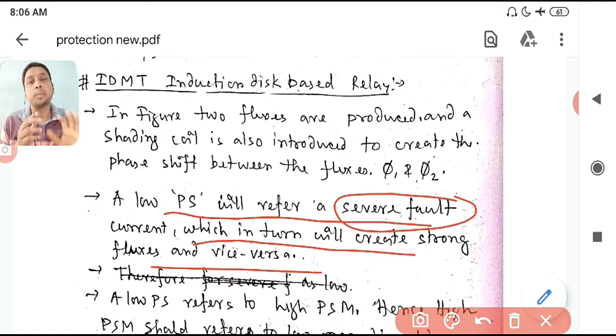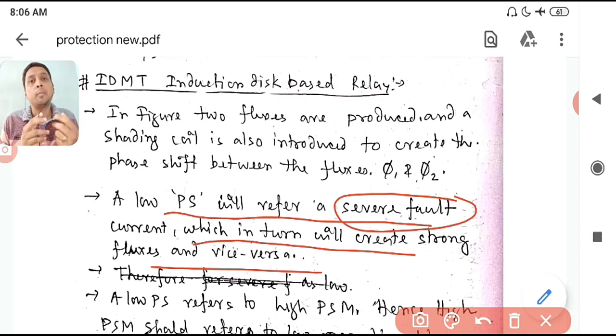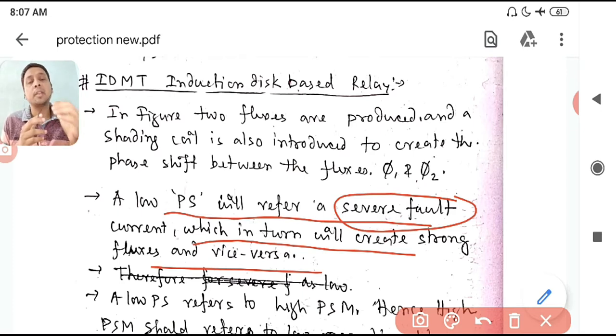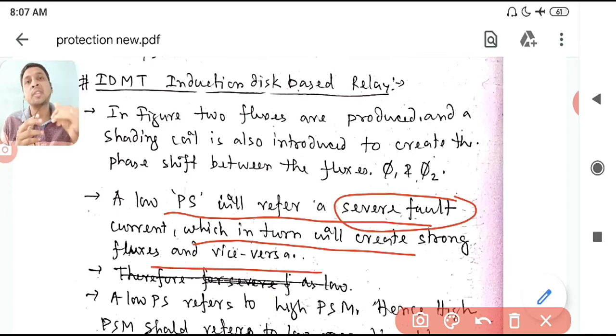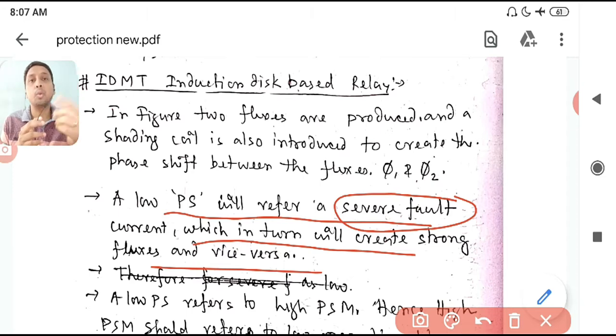For example, suppose your plug setting is 5 A and there is a fault of 10 A, then the PSM is 2. If your plug setting was 10, the PSM would be 1. Now if your plug setting is 2 and fault current is 10 A, the PSM will be 5. Setting it at 2 means the same fault is treated as more severe, because 10 is much above 2. If your setting is 5, it is still severe but not as severe as when the threshold was 2.